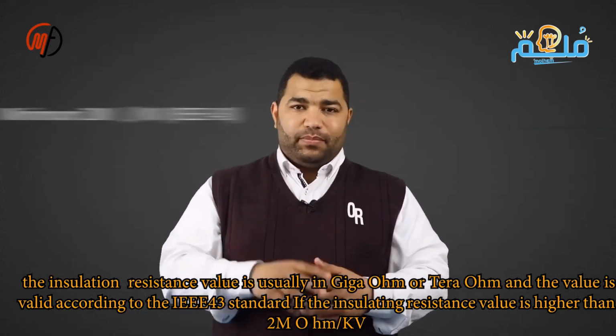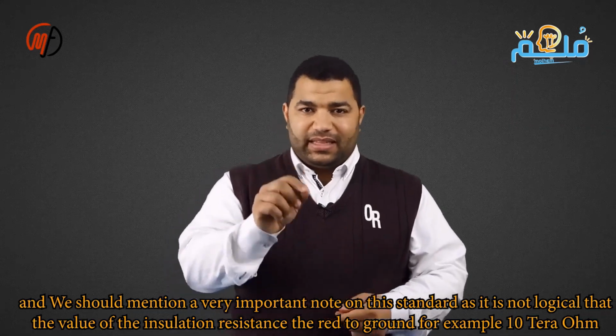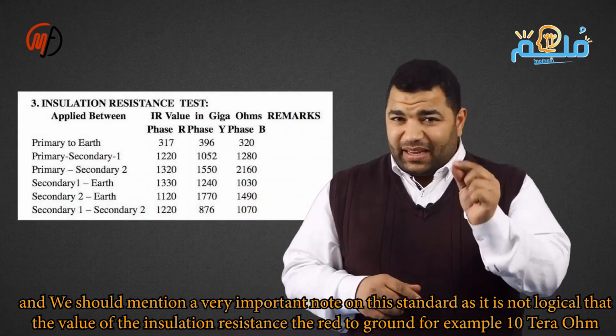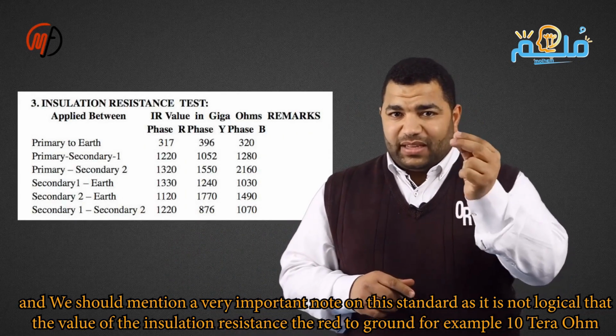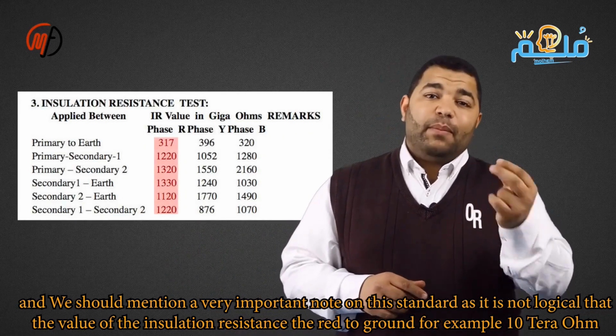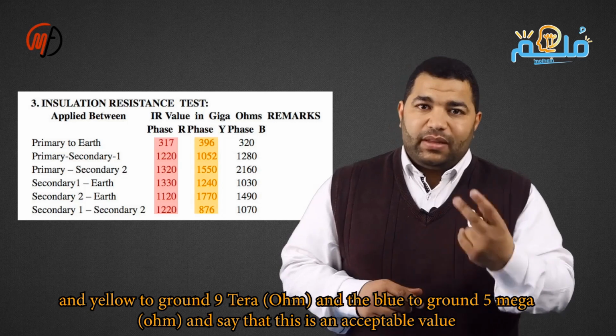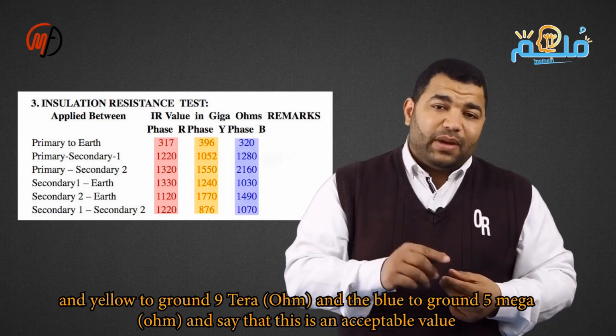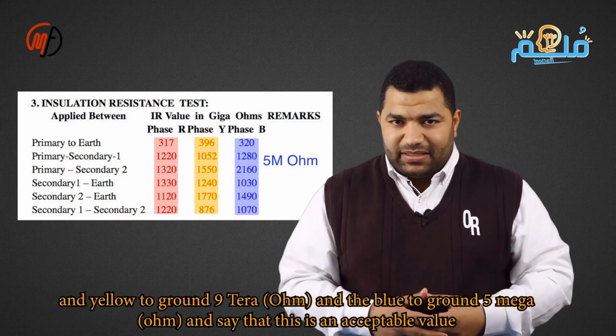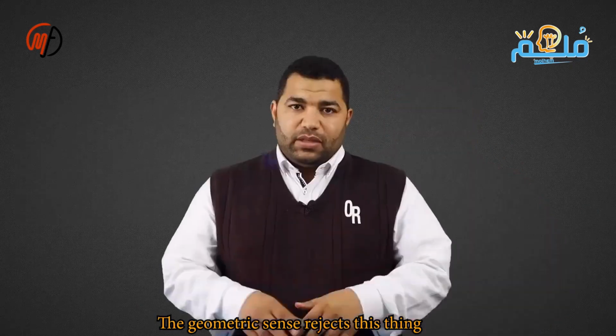It's important to note a very significant point regarding this standard. Red to ground at 10 tera ohms is illogical if yellow is 9 tera ohms. For example, if the yellow to ground is 9 tera ohms and the blue to ground is 5 mega ohms, and you tell me that this is an acceptable value, then common sense rejects this.